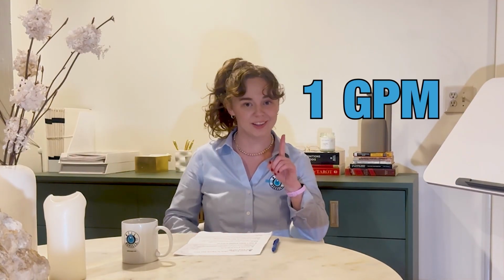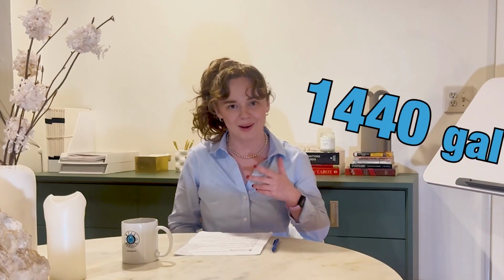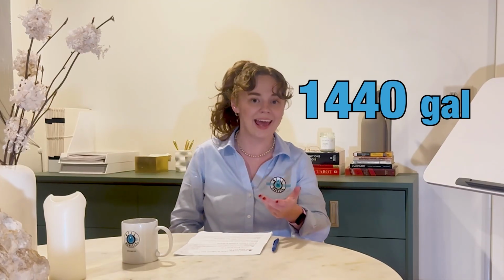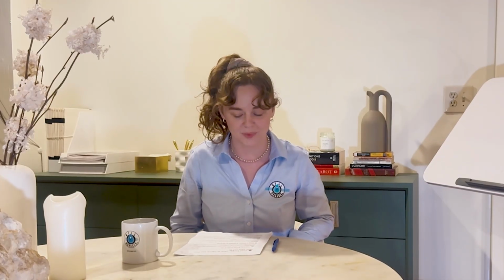And that'll help you size the correct system for a storage tank that can give you that water, be the buffer in between the well and the home. For example, a 1 gallon per minute well can produce up to 1,400 gallons a day if stored correctly. We'll get into that later. Now, most homes at their peak demand use anywhere between 6 and 12 gallons per minute. So if you think about it, if you have a low yielding well, you can start to understand why you're seeing these challenges, usually on a daily basis.